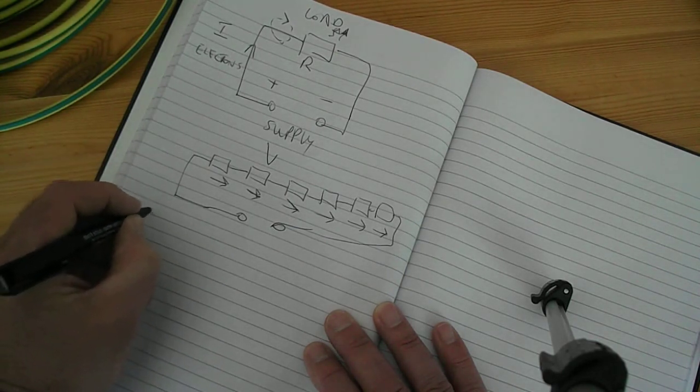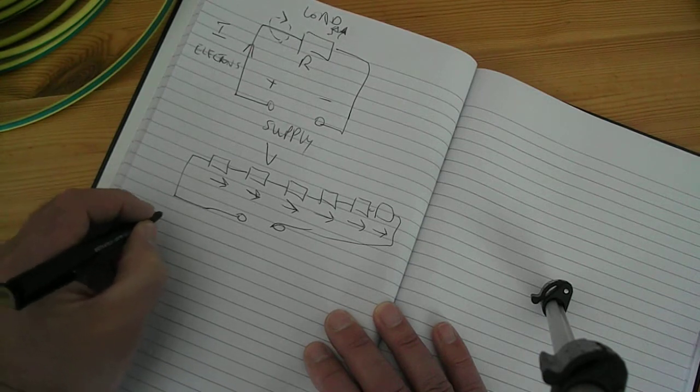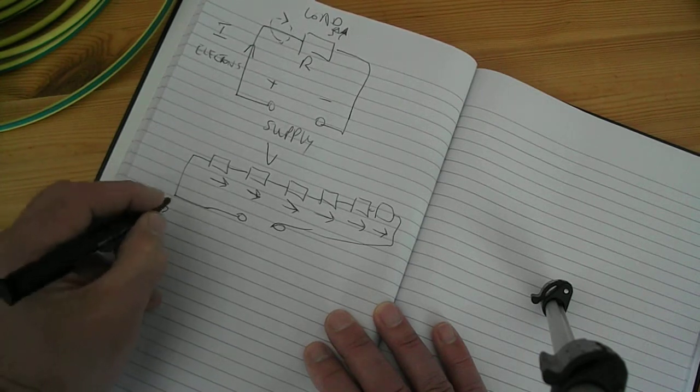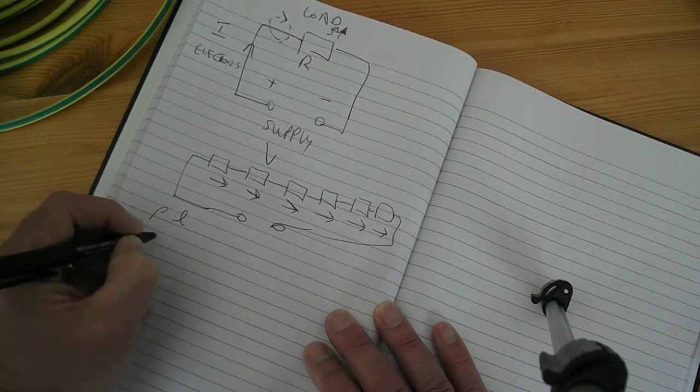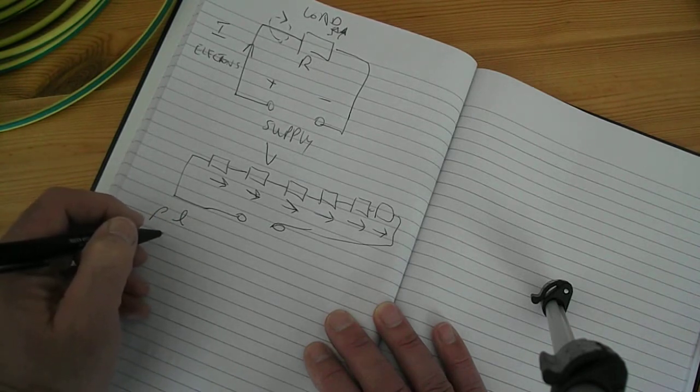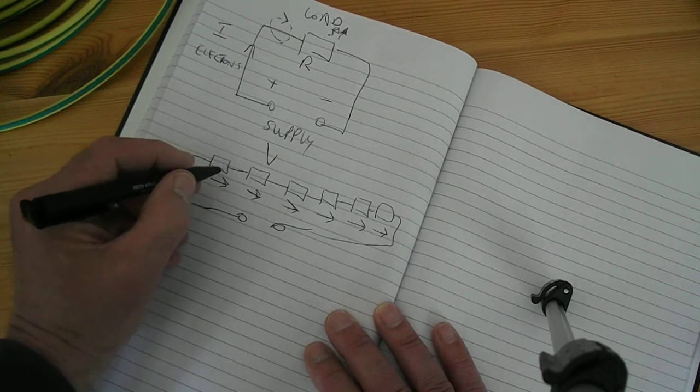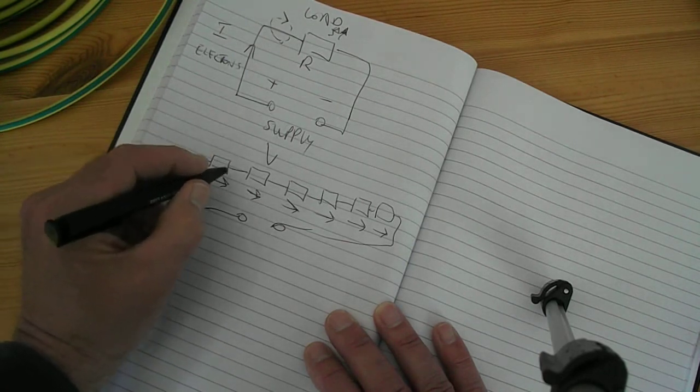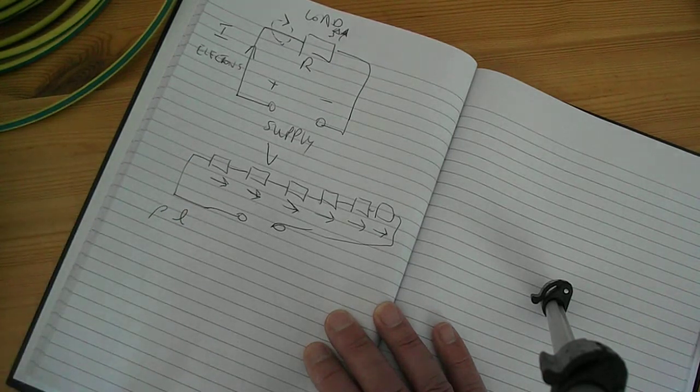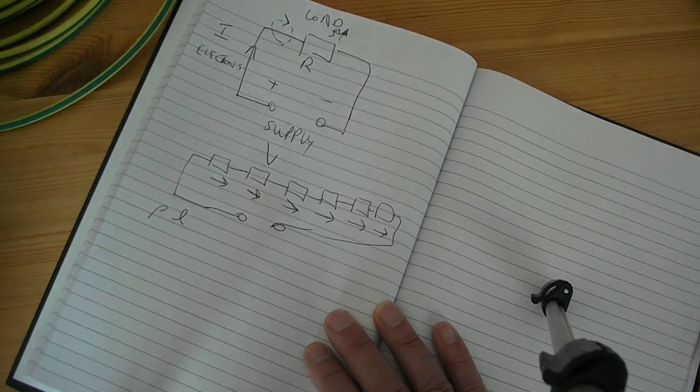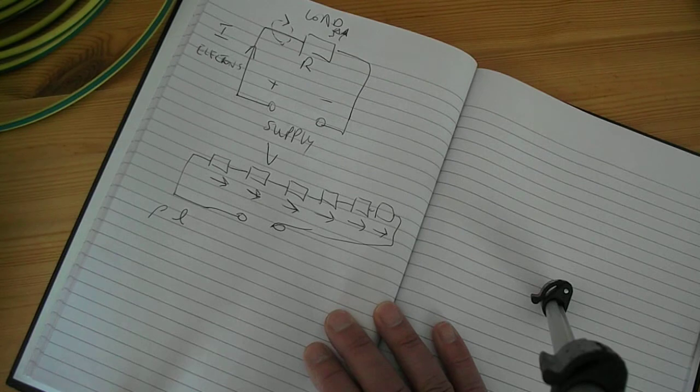So volt drop is caused by the resistance of the cable, or the resistivity of the cable rho, and also its length, and also its cross-sectional area. But it's mainly the resistance of the cable, and its cross-sectional area, and its length that causes the volt drop. So the longer the cable, the greater the volt drop. The higher the current, the greater the volt drop. The higher the resistance, the greater the volt drop.